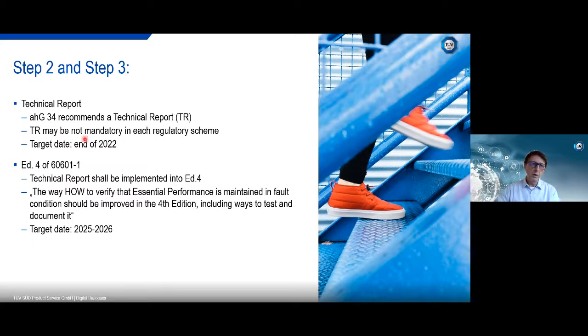And step number 3 would be this 4th edition of the 601-1 family, where all this information which is collected by now, and which will end up first in the technical report, will then be transferred to edition 4. And I would like to cite here the working group, saying the way to verify that essential performance is maintained in fault condition should be improved in the 4th edition, including ways to test and document it. So this is, let's say, the hope, at least of us at TUV, that we have here more clear requirements on how to address this issue. Target date, as mentioned, is 2025, 2026 for this edition 4 of 60601-1.